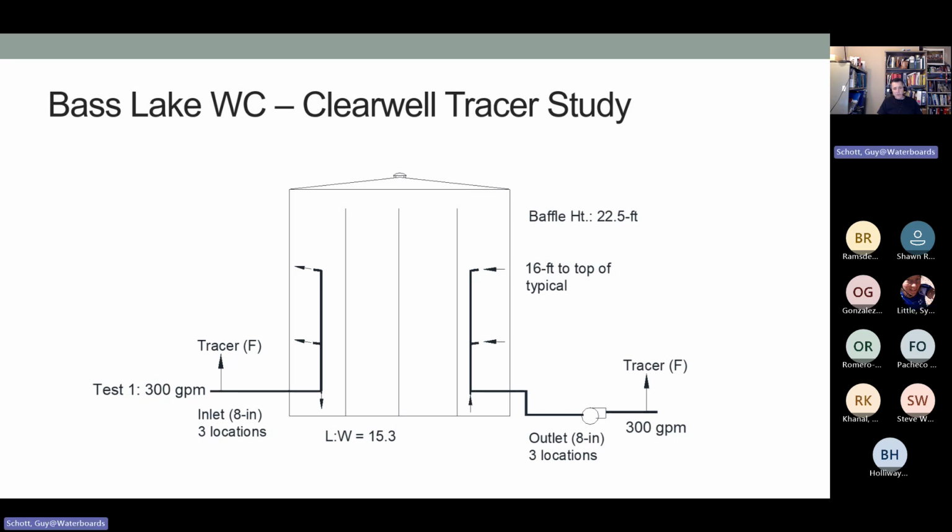Yeah. So Cindy was saying if this had a bypass here, you would do your tracer study, but what would happen is, say some of this water is being bypassed. Let me back up a little bit. Let's say you had a bypass, you'll still get your 10%, but that may come later, and somebody who's not experienced might think the results are fine.